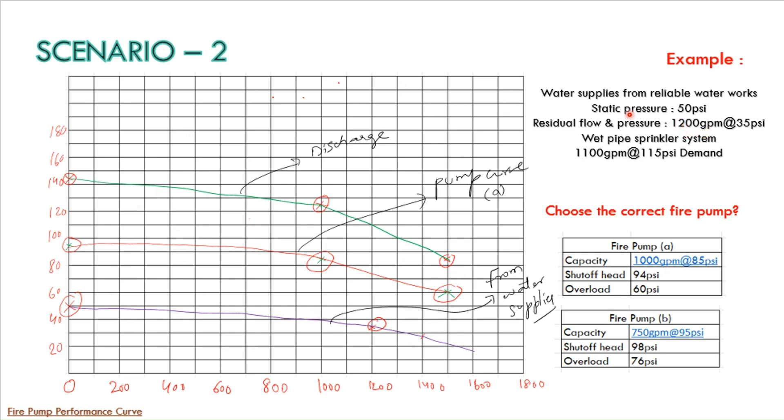We have taken the static pressure readings, residual flow and pressure reading and marked on this particular graph. If you see here static pressure is 50 PSI. So at zero flow it will be 50 PSI we have marked here and residual flow is 1200 GPM at 35 PSI. Then we joined these two points and extended this particular line.